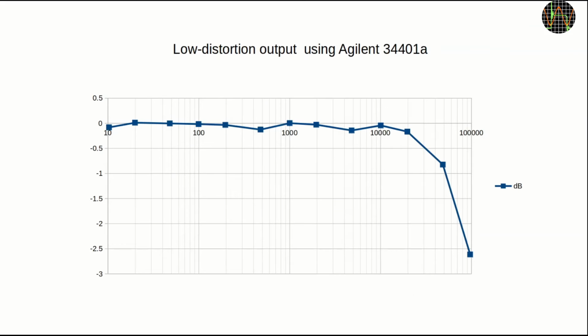As with the other graphs, I used my Agilent 34401A for the measurement of the low distortion output on the rear, expecting a similar picture as before. To my surprise, this was not the case, as you see here. Quite a significant drop starting slightly above 10 kHz. How could that be, since the same oscillator is feeding the other 2 outputs with no problems?